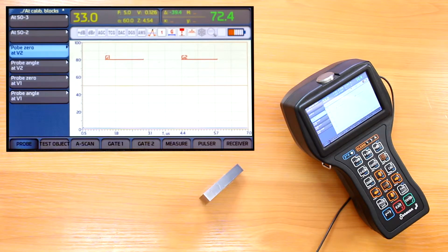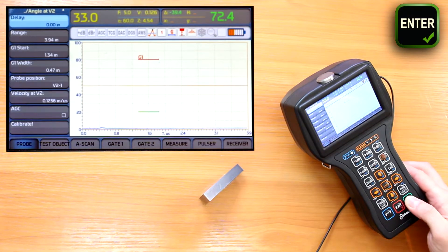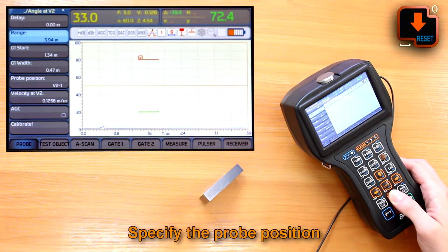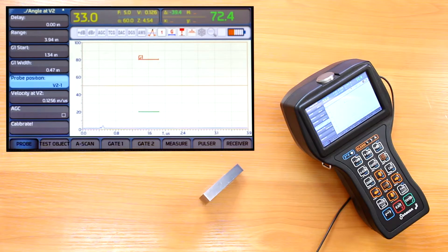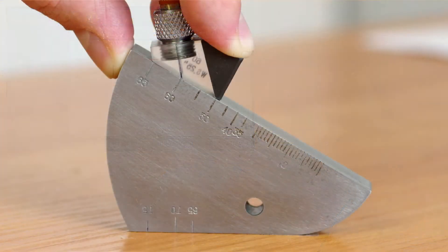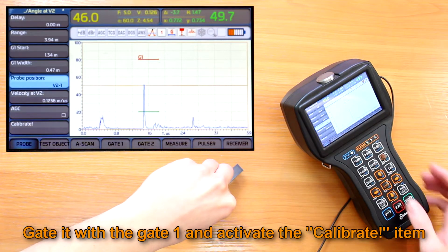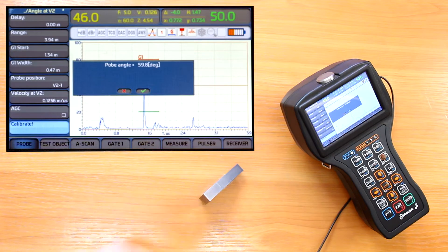We continue with calibration of the probe angle at the same standard, choosing and activating the 'Probe angle at V2' item. Since my probe angle is below 65 degrees, I use the upper working surface of the V2 and set the probe position to V2 1. Note that V2 2 is used for probes with an input angle above 65 degrees, and sound velocity is supposed to be already calibrated. I find and maximize an indication from the 5 mm diameter side drilled hole, then gate it with gate 1 and activate the calibrate item.